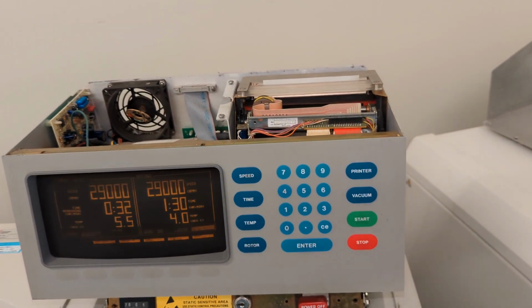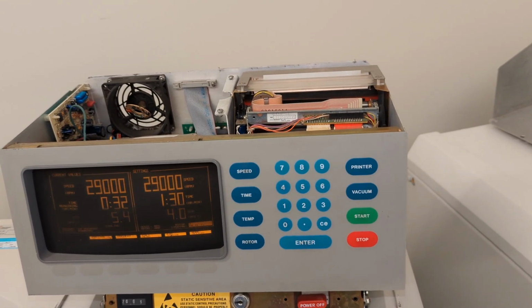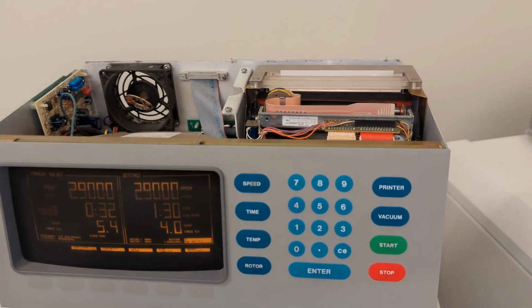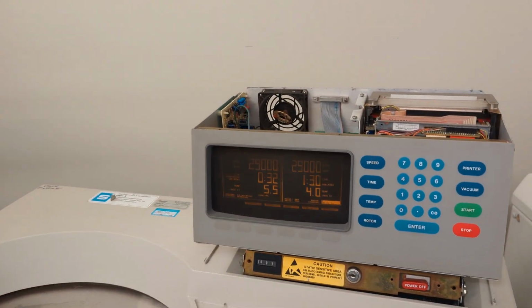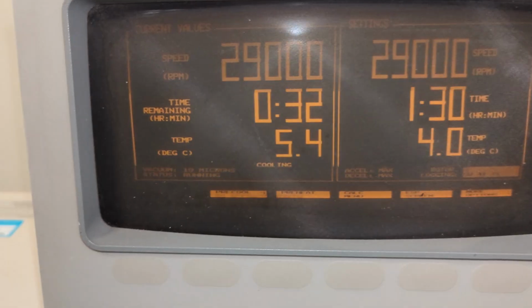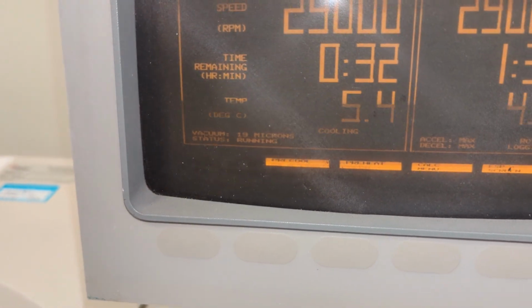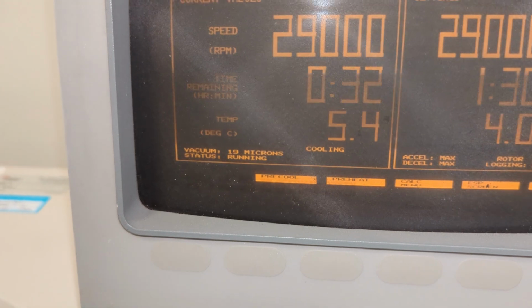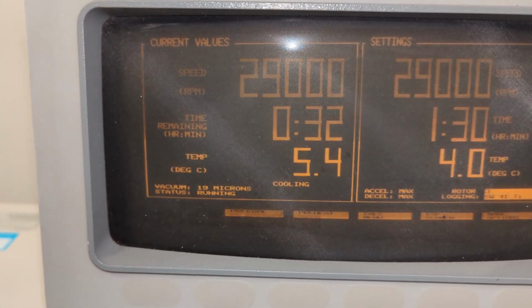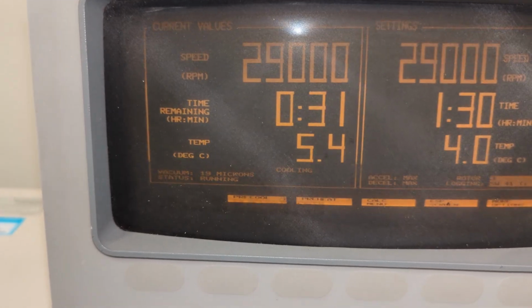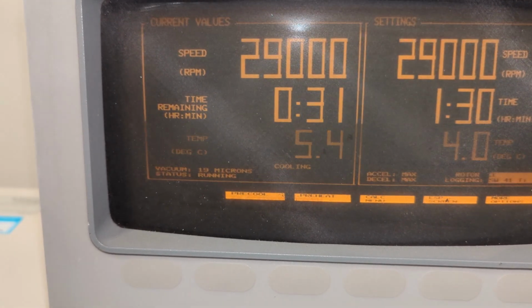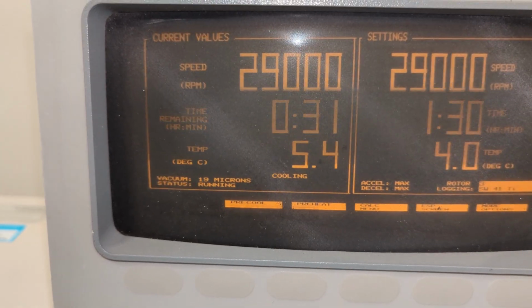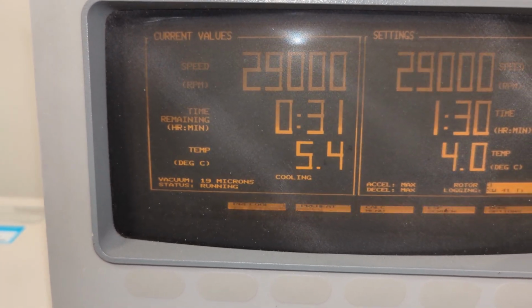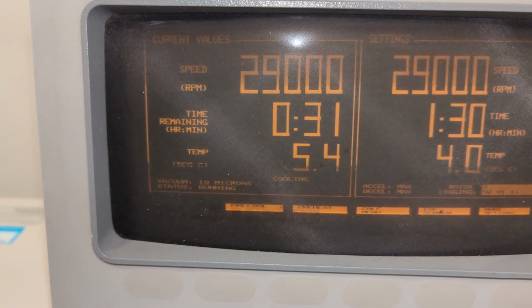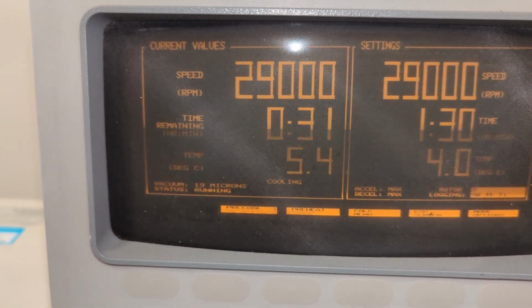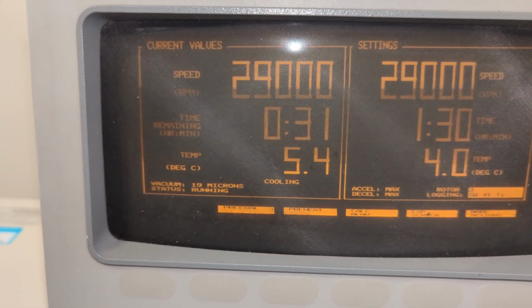We don't use this in a regulatory environment where we would need that kind of documentation, so not too concerned about that. But another problem that isn't related to the XL controller is the vacuum. You can see here we're measuring 19 microns. This unit started developing, about a month or so ago, this error 41 that would pop up during runs, which is basically just stating that the vacuum is between 20 and 750 microns. It's not an error that's enough to prevent the unit from continuing the run, so you just have to acknowledge it and it'll keep going.